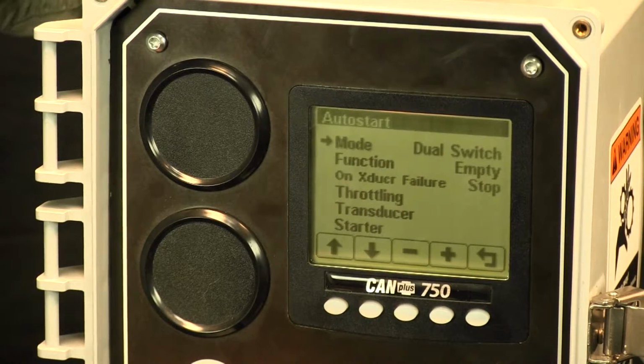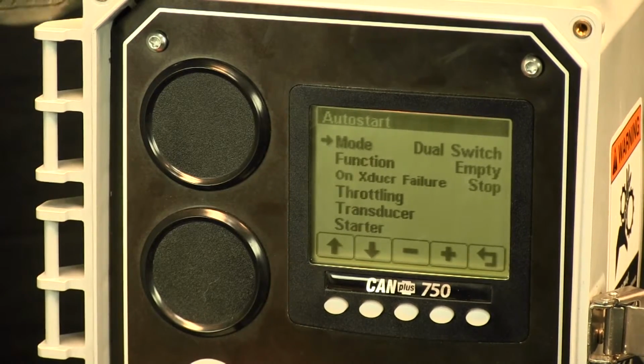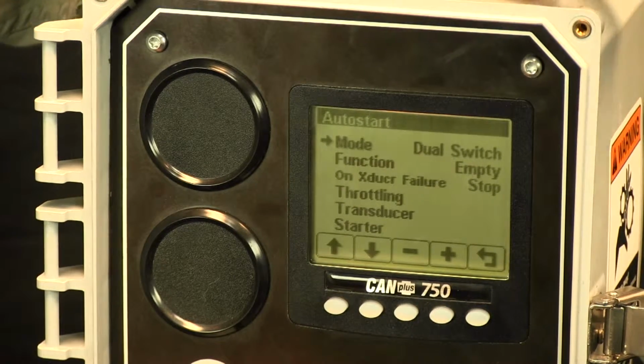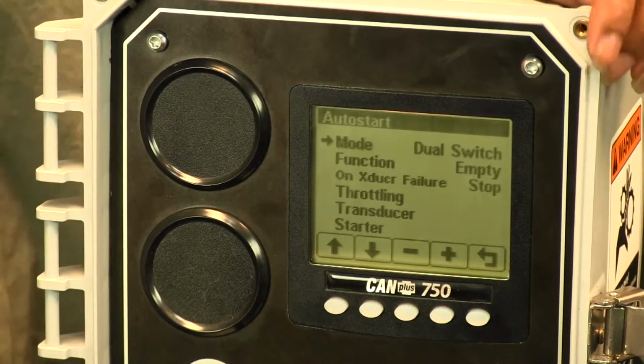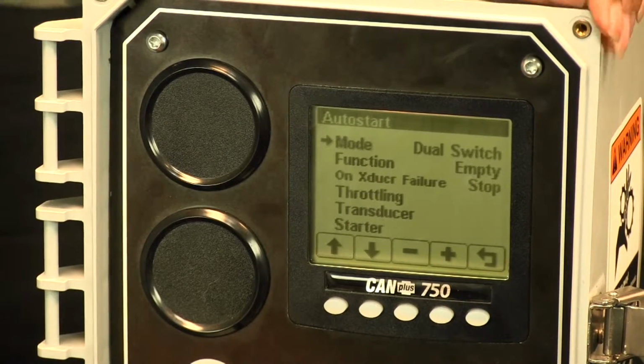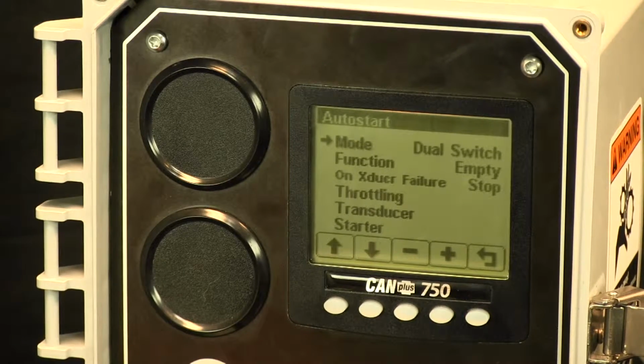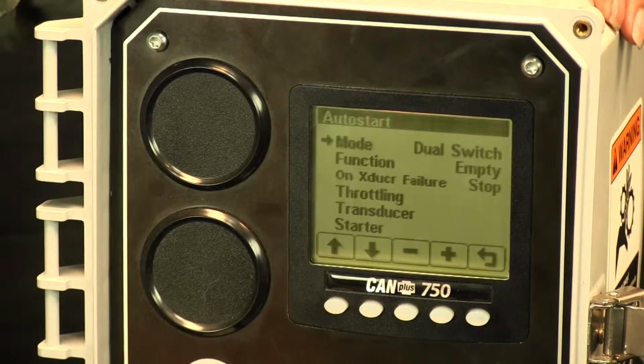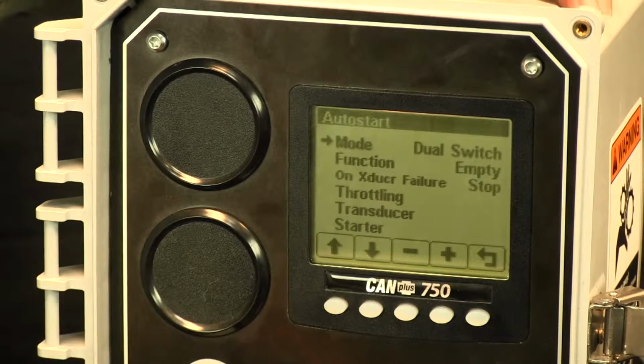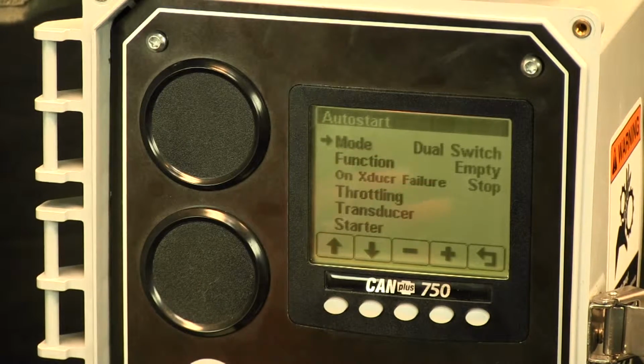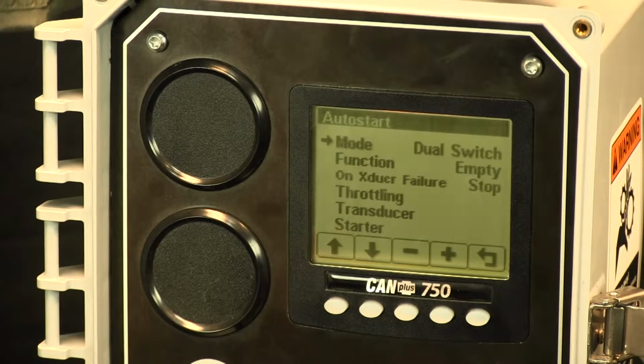Okay, so the differences between dual floats and single floats is if you were to use a single float and possibly say put it in a pond, and say if it was a little windy, you'd probably hear your engine going on and off, always starting and stopping, starting and stopping due to using only one float due to the choppy waters. But if you were to place dual floats in a pond and you were to place one at a low level and another at a high level, as soon as the low level float gets armed, then it's in its start event, and it'll wait for that high float to close as well in order to start an event.